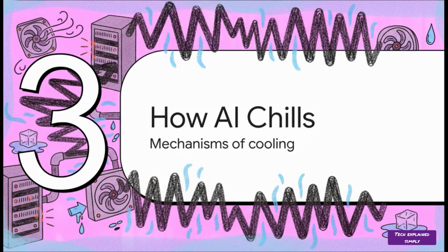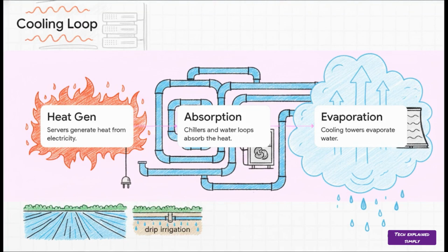So how does AI infrastructure actually chill out? Well, the process generally follows a standard evaporative cooling loop. Step 1, the servers generate heat from electricity. Step 2, chillers and internal water loops absorb that heat. And step 3, that warm water is pumped out to massive cooling towers, where some of it is evaporated right into the atmosphere to reject the heat outdoors. It's highly effective, but man, is it water intensive.